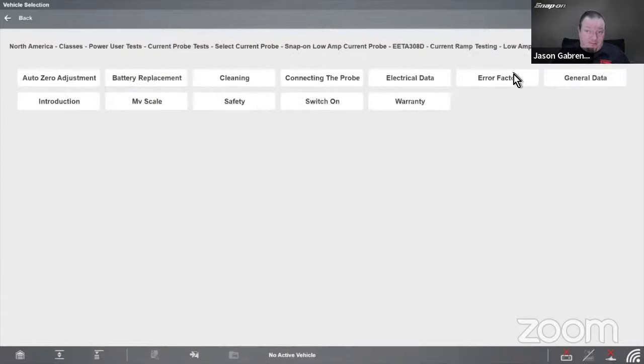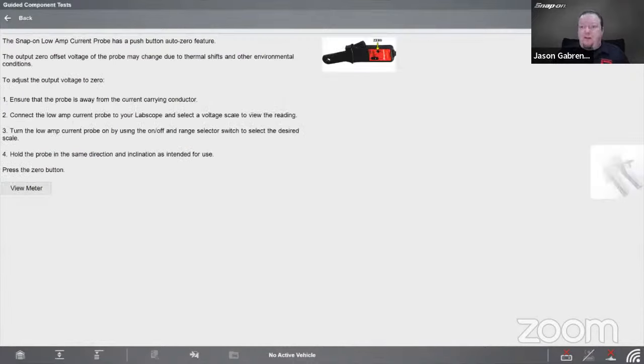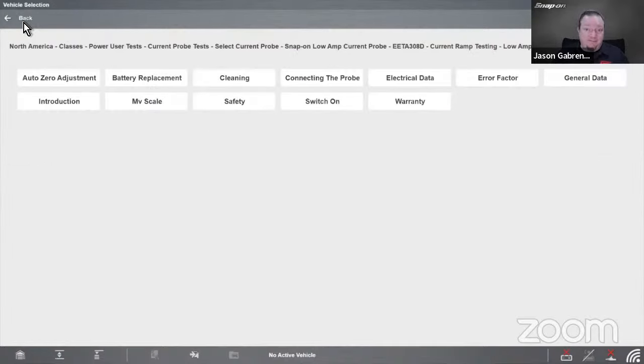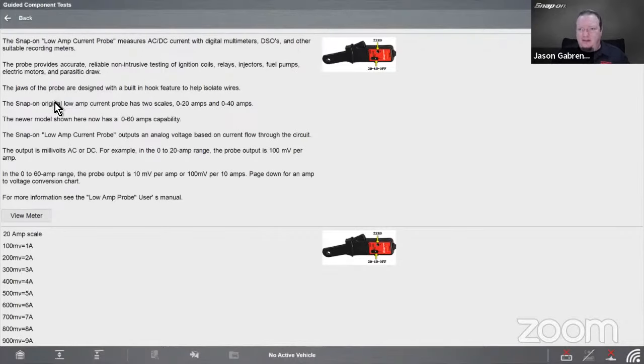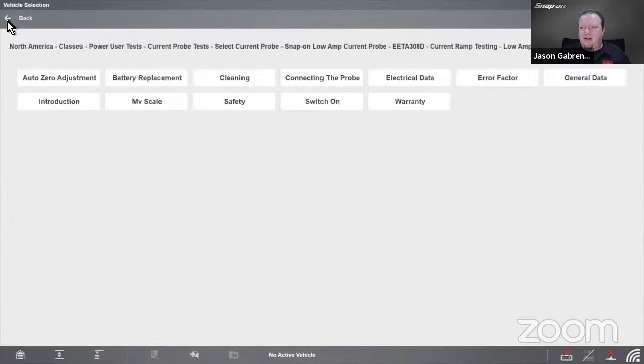The manual is in here, remember how I talked about that? So if we go to auto zero adjustment, like I mentioned before, to adjust the output voltage to zero, ensure the probe is away from the current carrying conductor. Connect the low amp current probe to your lab scope and select a voltage scale to view the reading. Turn the low amp current probe on using the on-off switch, hold the probe in the same direction and inclination as intended for use, then press the zero button and it'll zero it. I mention this because I don't think it's explained elsewhere - the Earth's magnetic field can do weird stuff, so we just want to make sure we account for that.